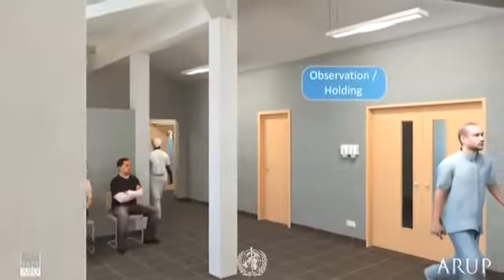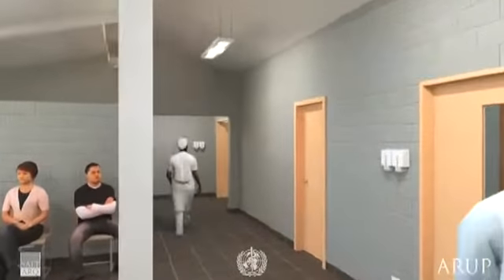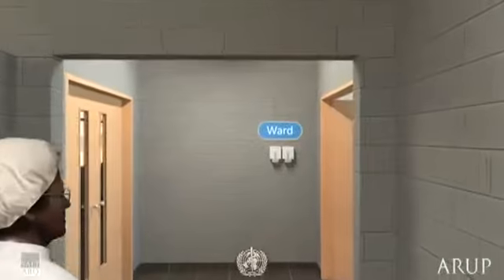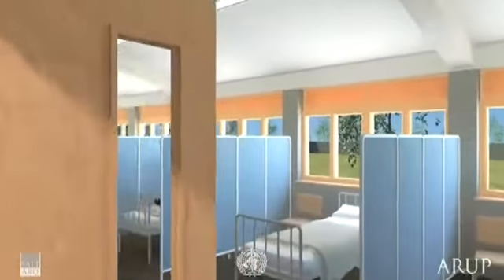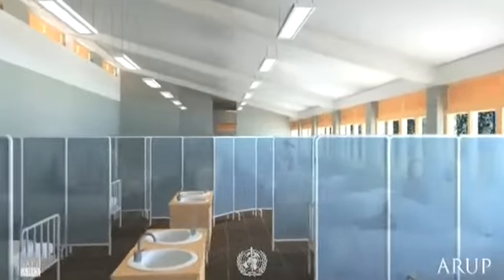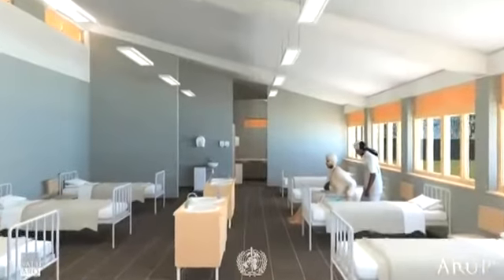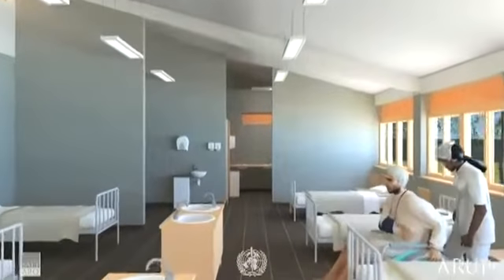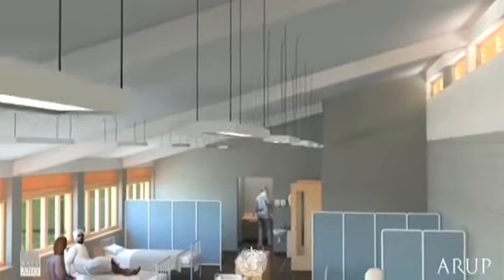We also wanted to look at thermal comfort of patients, including the clinicians who will be fully gowned. We found that because this hospital is so close to the equator and therefore the sun's very high in the sky, shading from nearby trees actually had hardly any effect. So what we suggested to the architects was that they could increase their roof overhang and create a shaded walkway, and in doing so that would help to shade those southern windows.